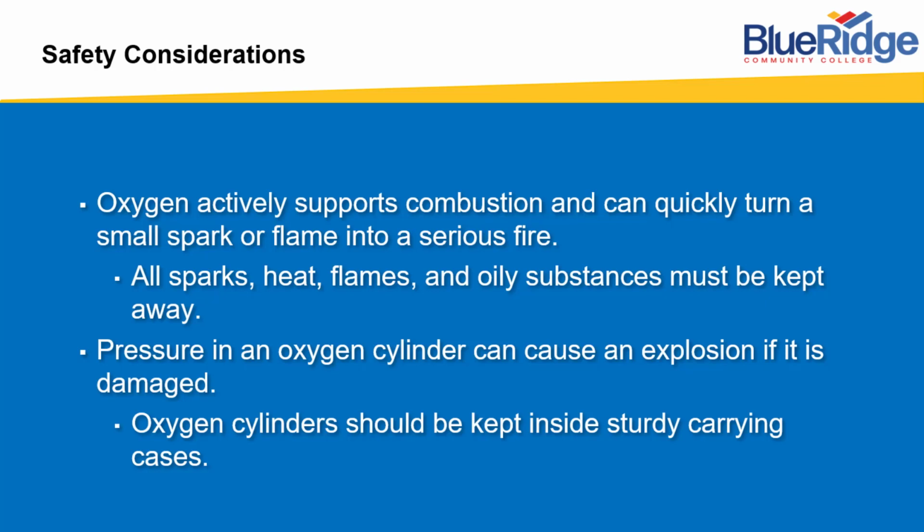All sparks, heat, flames, and oily substances must be kept away from oxygen equipment. In mechanical industries with welding and metal fabrication, or diesel mechanics and things like that, when swapping out oxygen for cutting torches, we always make sure that the tops of the bottles are clean and dry from any kind of oil or residues before swapping those regulators out, just to reduce the risk of there being any ignition of a substance that might be resting on the outside of that bottle. Obviously, smoking is never safe around oxygen equipment.